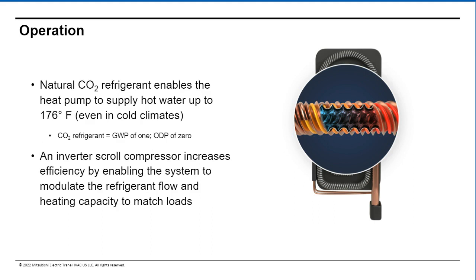Because it's CO2 based, we're able to do really high hot water temperatures compared to a lot of traditional HFC products. We can do up to 176 degree water leaving the heat pump. And we can do that all the way down to negative temperatures out in the marketplace. We rate the product at -13, but it can actually run all the way down to -35, which is one of the big benefits of using CO2. Paired with that, we use technologies we have today in our VRF product, having the inverter compressor and flash injection like you would see on our hyperheat products, to further improve heating performance and COP at low ambient conditions. That's really one of the big differentiators, how well we can perform at low ambient conditions for the product market.